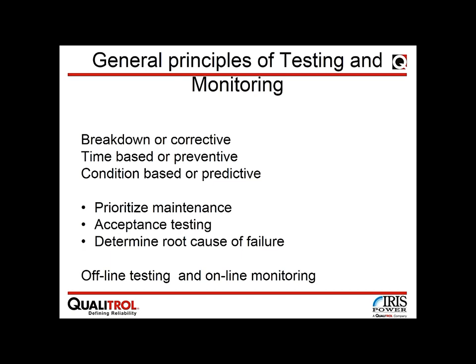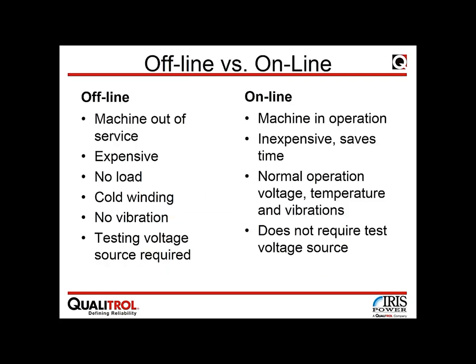An important distinction is between offline testing, where the machine is stopped and instruments simulate conditions for measurement, and online monitoring, where the machine is working and instruments — periodic or continuously installed — monitor the winding or rotor condition. There is also a difference between monitoring and protection: protection stops the machine to minimize damage, while monitoring improves knowledge about condition without tripping the machine from service.